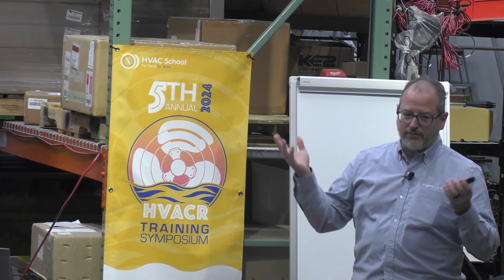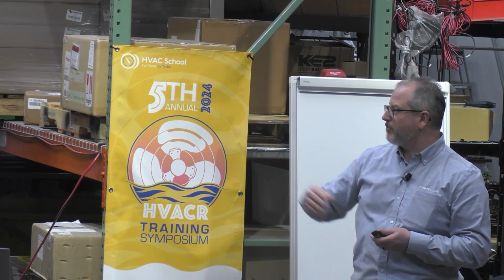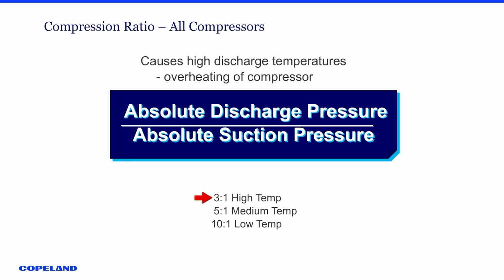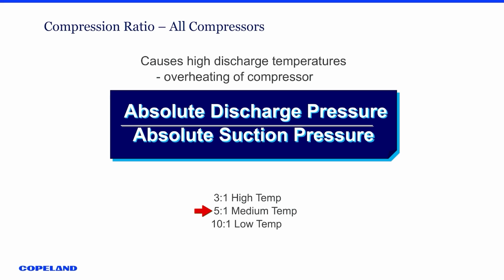Somebody came up with these numbers for us. When we talk about high temp, again, we're talking about air conditioning or high temp refrigeration, we want a compression ratio around 3 to 1. Okay? It's always going to be to 1, whatever that number is. Okay? Medium temp refrigeration is going to be 5 to 1. Okay? And then low temp will be 10 to 1.